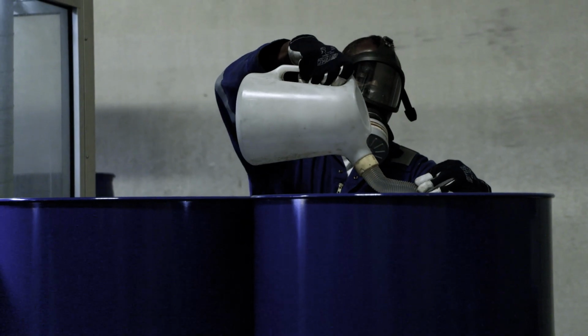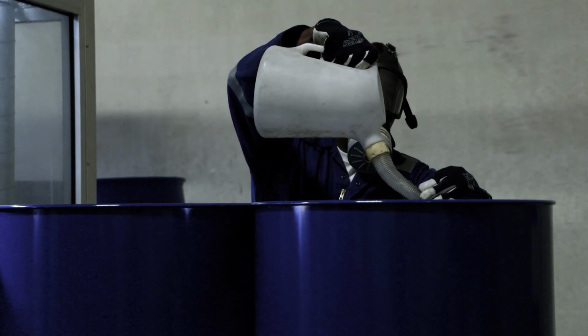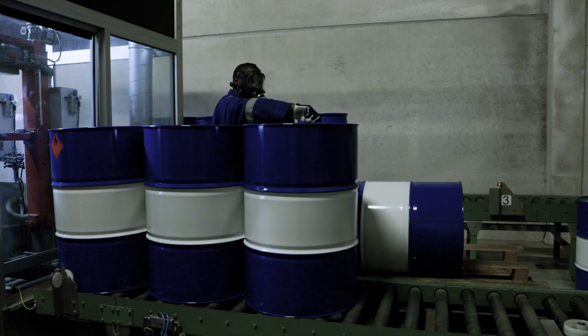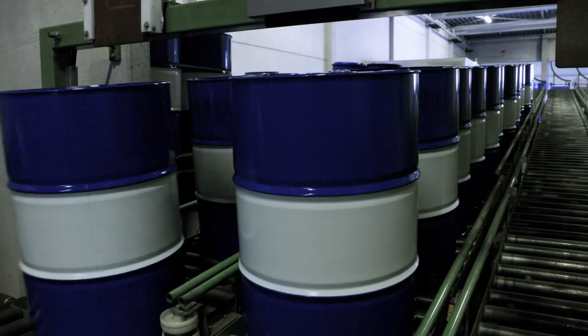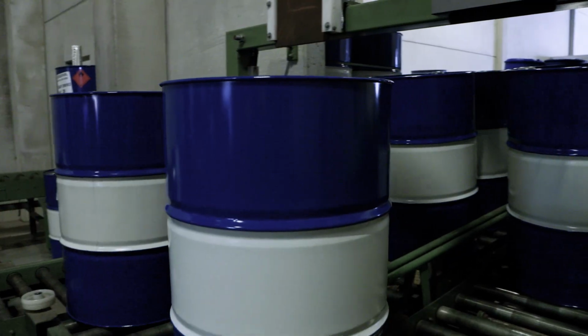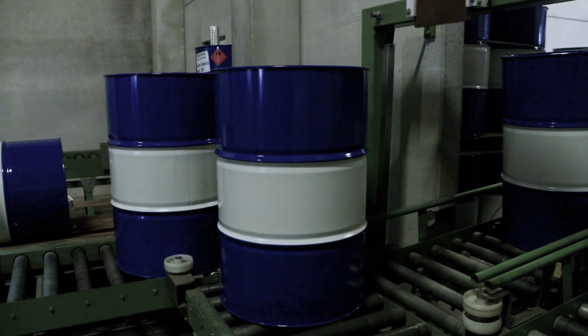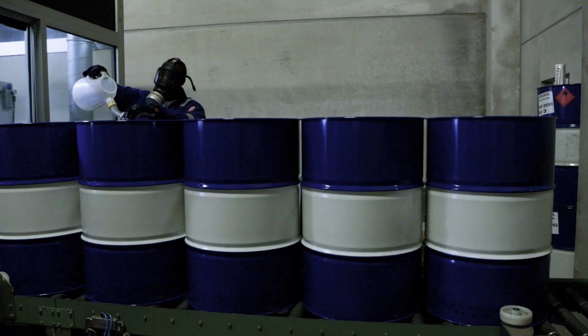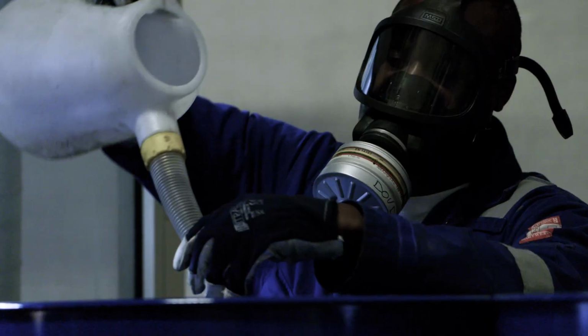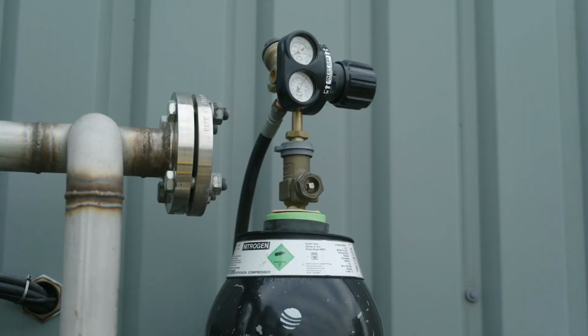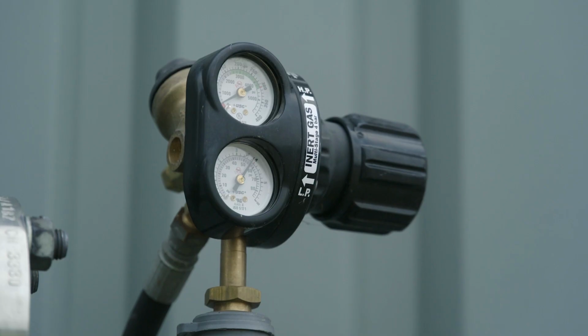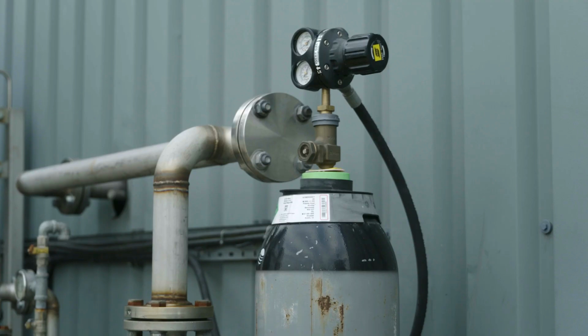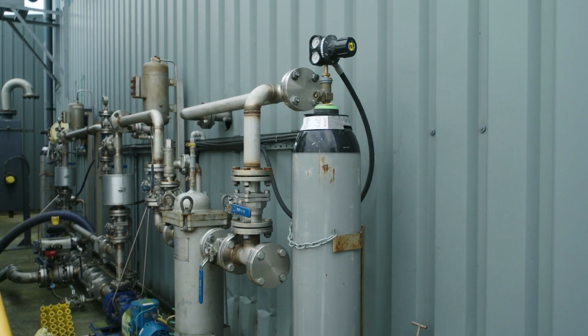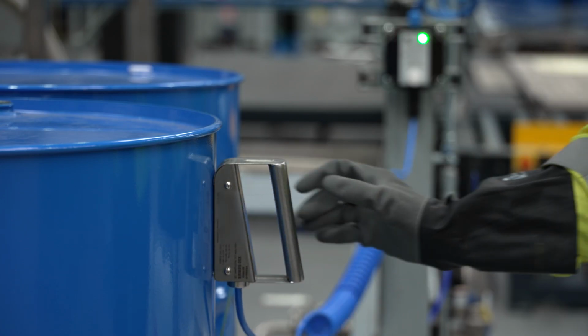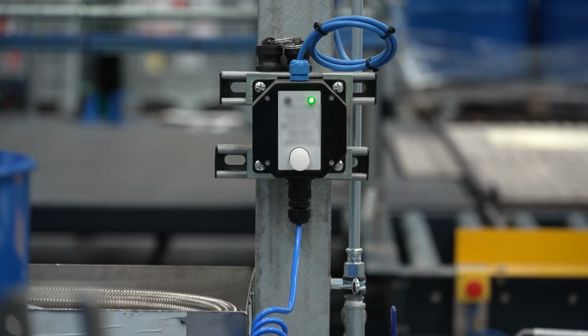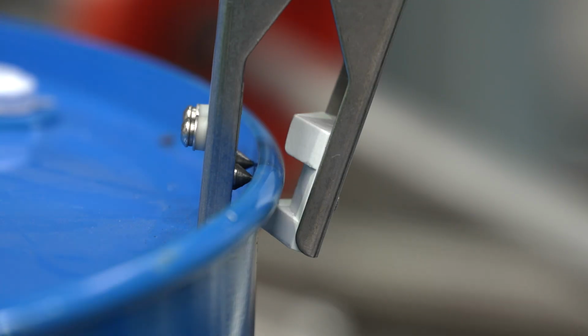In some cases, anti-static agents can be added to reduce the charge accumulation. Typically, only a few parts per million are required. Assessment of the suitability of such additives with each formulation is advised. If additives are used, they should always be used in tandem with an appropriate earthing and bonding procedure. Inert gas blanketing for vessels and pipes should be considered to minimize the presence of explosive atmospheres in the vapor space. Earthing and bonding is a very effective technique for minimizing the likelihood of an ignition caused by static electricity.